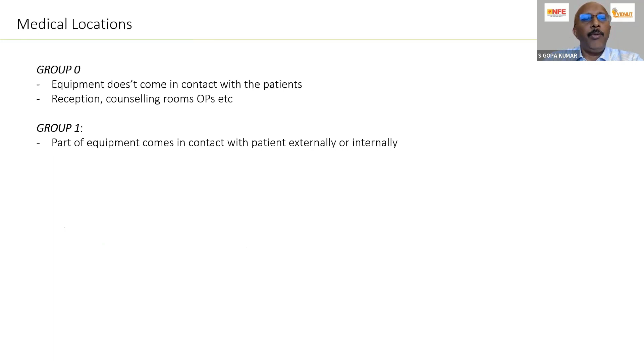Group 0 is a medical location where the equipment doesn't come in contact with the patient, the normal area. Group 1 is an area where part of the equipment comes in contact with the patient externally or internally, mostly on the surface of the body. Some biomedical equipment are sometimes connected or used for certain checks.